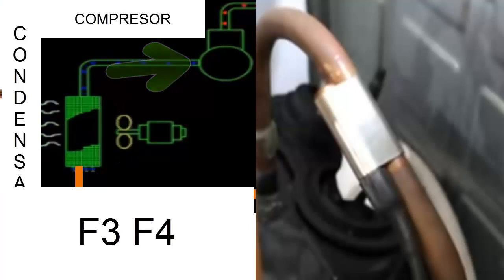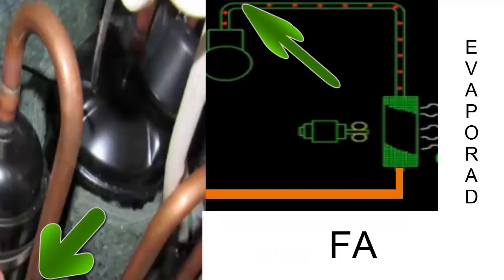Finally, we will find the sensor that measures the temperature of the refrigerant at the suction of the compressor. This sensor can help us control the overheating of the refrigerant and thus improve efficiency. These systems control overheating because controlling overheating will directly increase efficiency. If we have minimum overheating, the efficiency of the air conditioning will be greater. When this sensor has a problem, the failure code generated is the code FA.